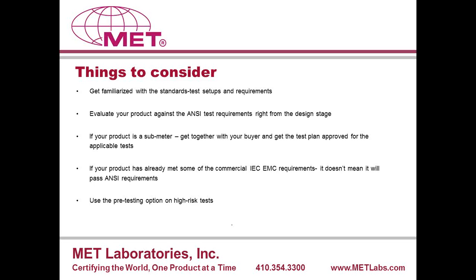And lastly, use the pre-testing option on high-risk tests. After you've gone through all the checks and through pre-testing back and forth with the local test labs, before you're even ready to submit your product for final ANSI C12 testing, you still have the option of pre-testing some of the high-risk tests so that you eliminate the risks. Thank you. With that, I'll pass over to Jim.